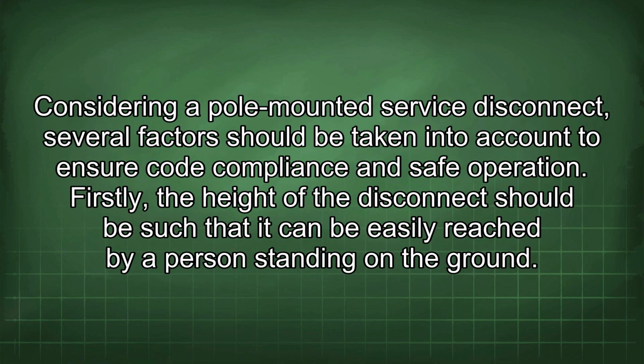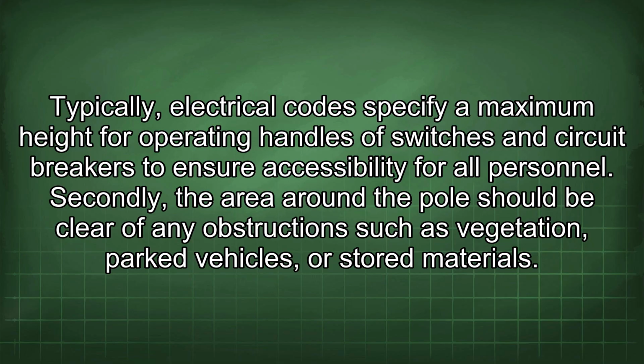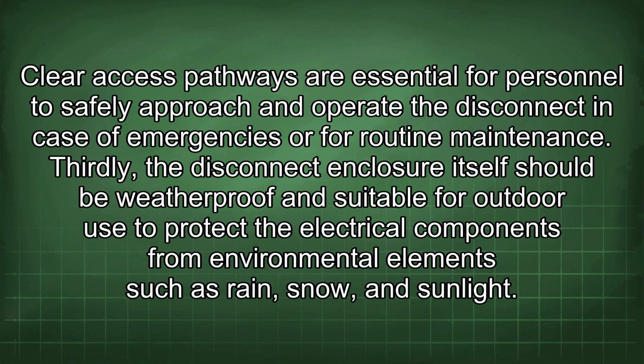Considering a pole-mounted service disconnect, several factors should be taken into account to ensure code compliance and safe operation. Firstly, the height of the disconnect should be such that it can be easily reached by a person standing on the ground. Typically, electrical codes specify a maximum height for operating handles of switches and circuit breakers to ensure accessibility for all personnel. Secondly, the area around a pole should be clear of any obstructions such as vegetation, parked vehicles, or stored materials. Clear access pathways are essential for personnel to safely approach and operate the disconnect in case of emergencies or for routine maintenance.